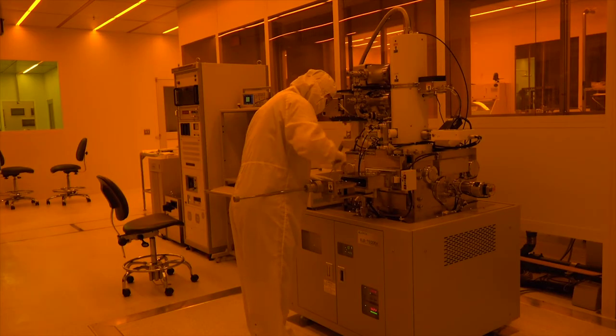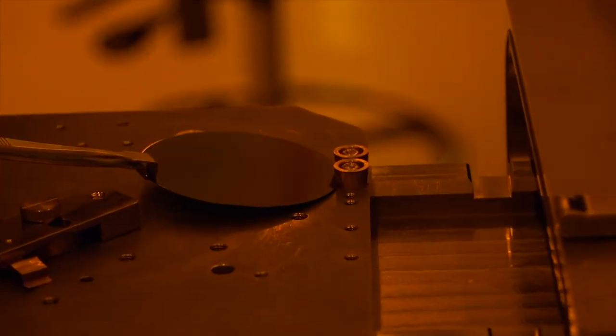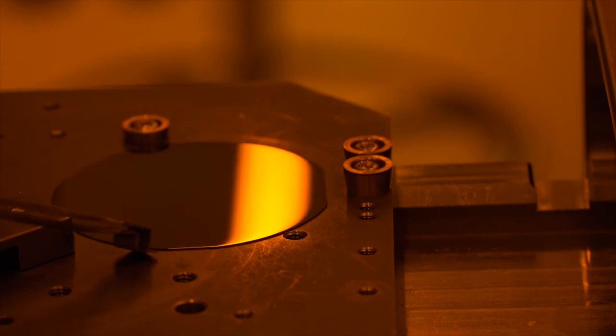The load lock is connected to the high vacuum EBL chamber by a door that we keep closed while we load our sample. This enables us to keep the EBL chamber under high vacuum while we load our sample into the load lock. There is a small platform in the load lock for holding our sample.